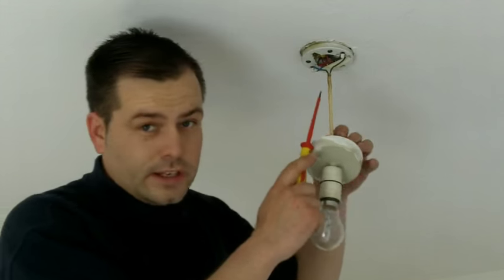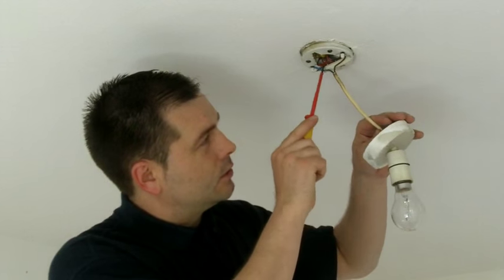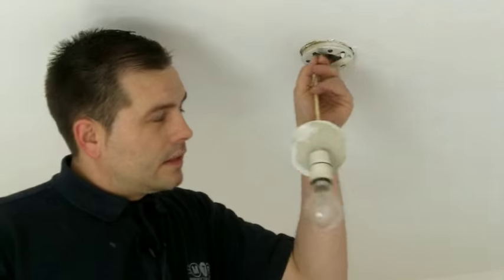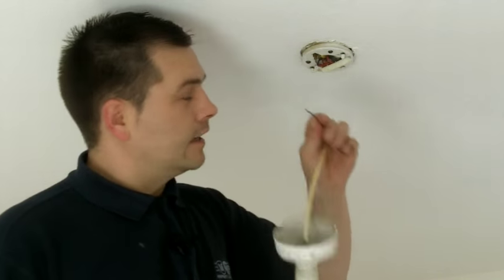You will see that this light fitting is actually connected up wrong. We have a blue joining onto a red cable and we have a brown joining onto a black cable. Now of course an electrical test would have picked this polarity issue up and it shows why it's always important to have an electrical test carried out on your home.